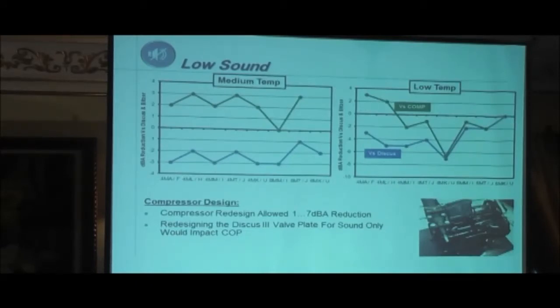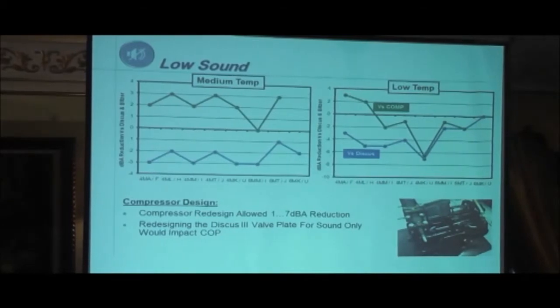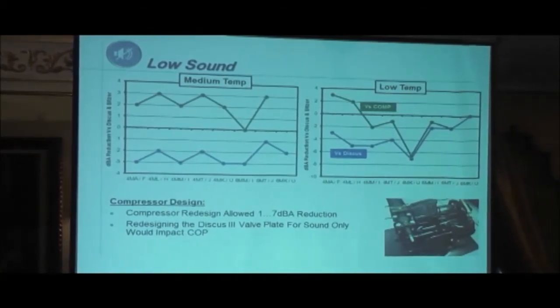In some markets, sound has become very important. So when we redesigned the valve plates, we modified the cylinder head. We've reduced the pulsations in the head, and by reducing the gas pulsations, we're able to reduce the noise of the compressor. And again, this is a comparison of one model of Copeland versus our competition.